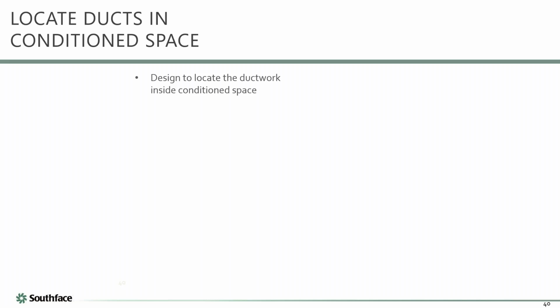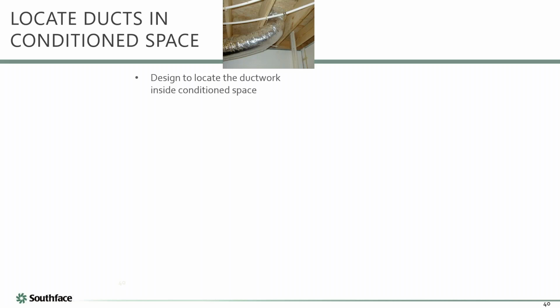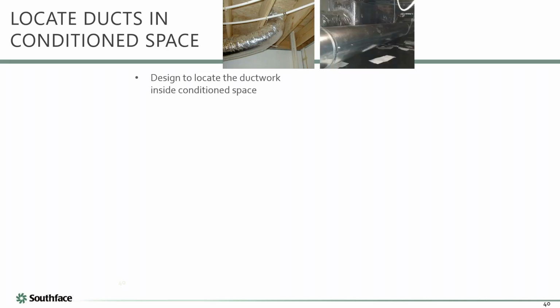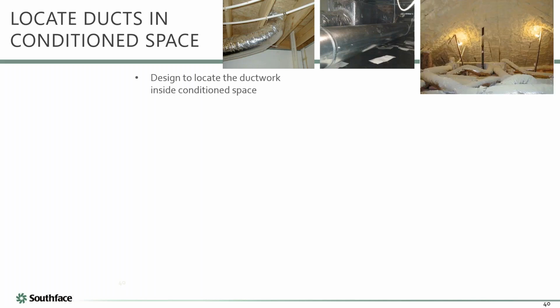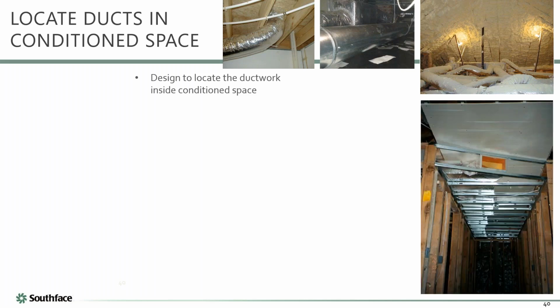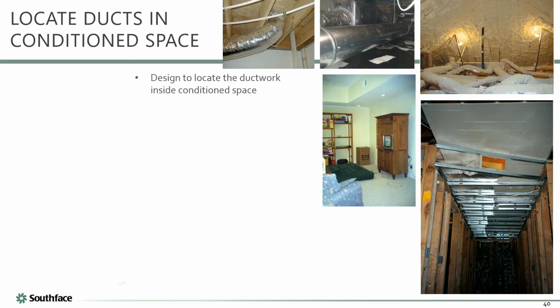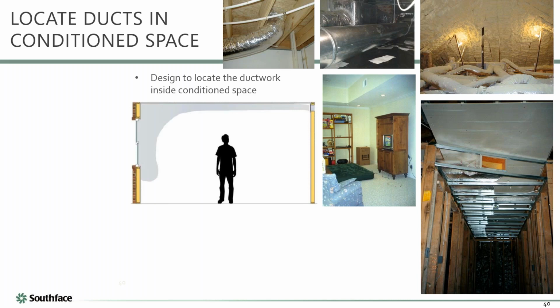All right, I made a collage for everybody. I hope you appreciate my artwork skills. How can I locate my ductwork inside the conditioned envelope? Well, I could put it inside a conditioned basement or crawl space where I've insulated the walls of the crawl space or basement. I could put it inside an attic where I have foamed the roof line. I could do a furr down detail in a hallway, for example, where I've got a hard air barrier, and then the hallway drops from 9 feet to 8 feet. I could essentially have a space to rough in my duct system after putting in a hard air barrier. I could do kind of a drop soffit that goes around a room.